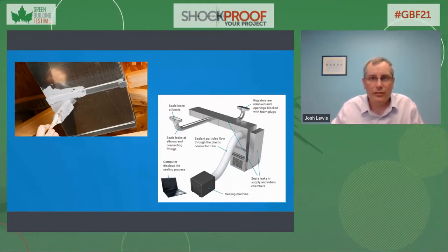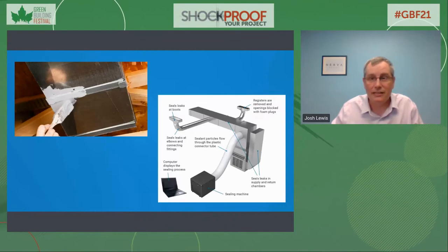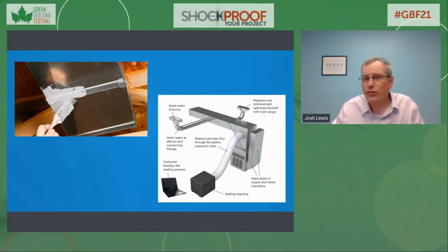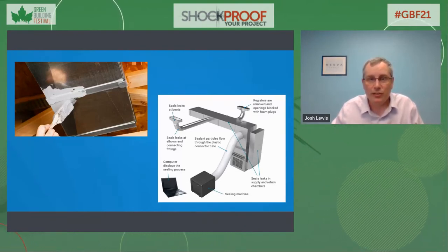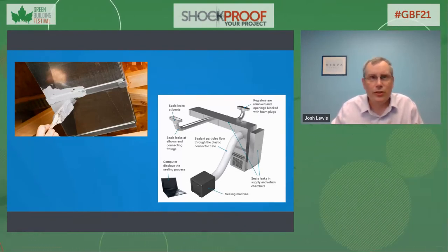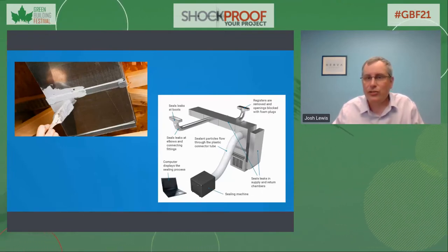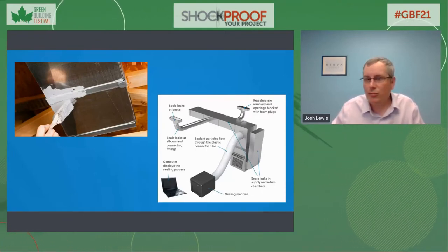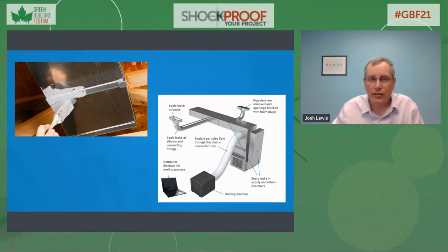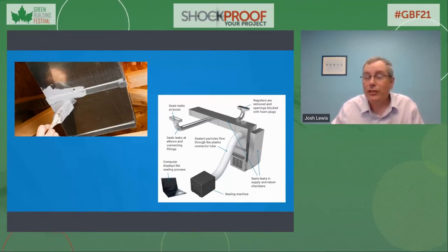Ductwork can also be sealed tighter in new and existing buildings through various methods, including the traditional method of using mastic tape and caulking with an extra level of attention to detail, and also through new technology now available to seal ductwork from the inside using a pressurized spray system. Regardless of which method is selected, ductwork sealing is one of the only strategies that can improve indoor air quality while also saving energy usage over the long term, creating the potential for a win-win scenario.